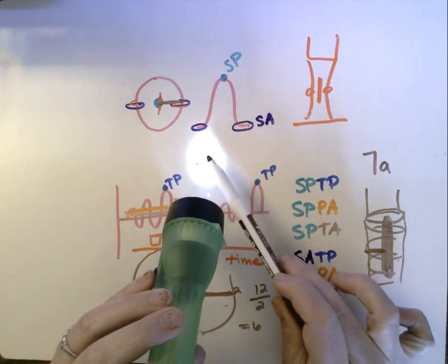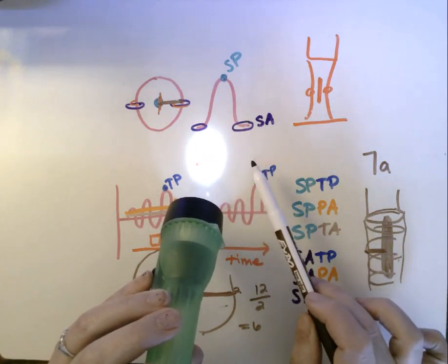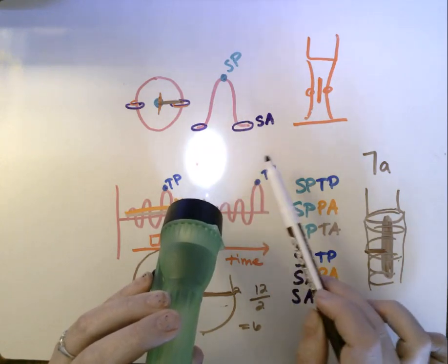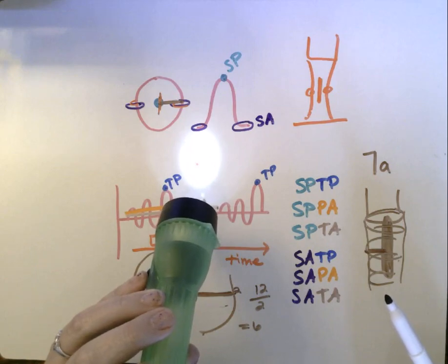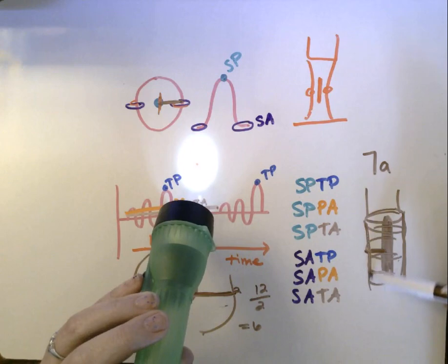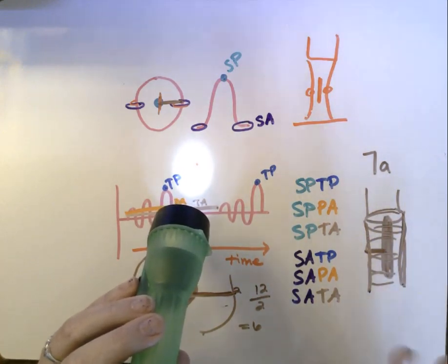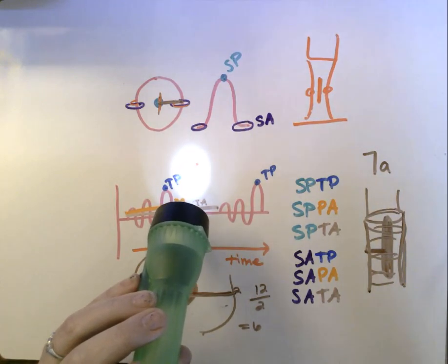Spatial peak is going to be right in the middle. Average is going to take those weak intensities on the edge and average them all together all the way across the radius of the circle. We need to think about the beam as coming out as a 3D expression of energy, and then recognize that there is a centerpiece and then weaker edges.